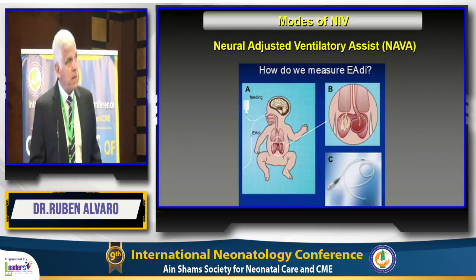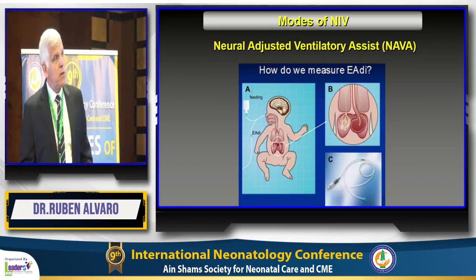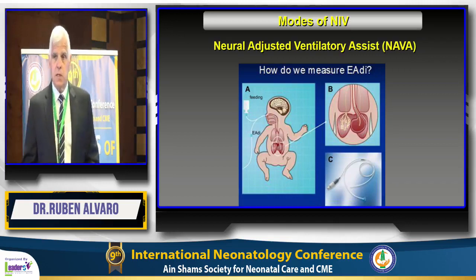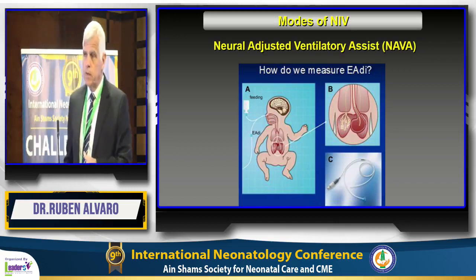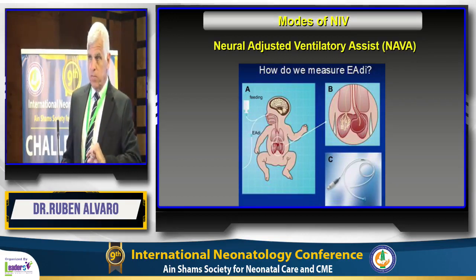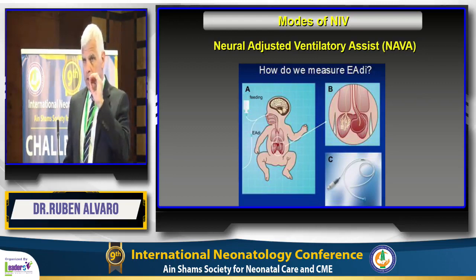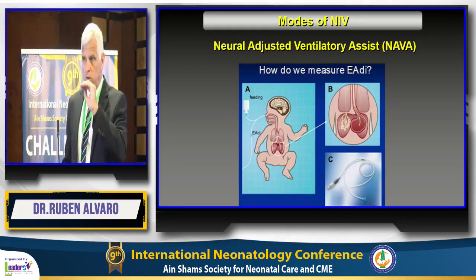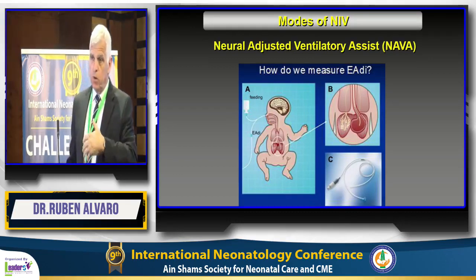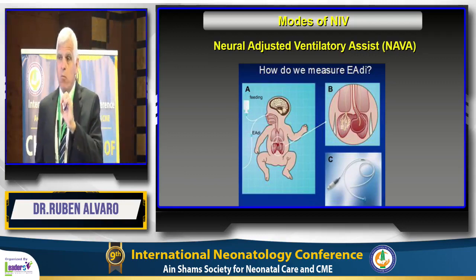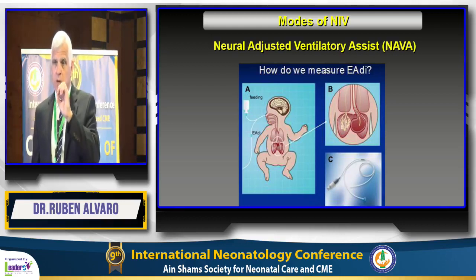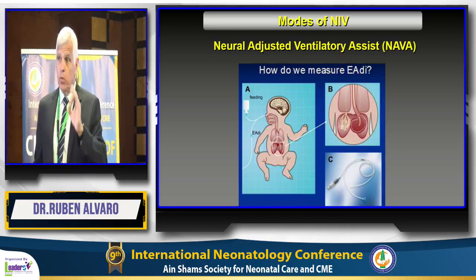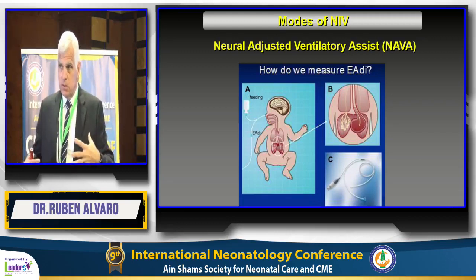You have an electrode that will detect the electrical activity of the diaphragm. It's basically a nasal tube with a sensor that sits behind the heart, just on top of the diaphragm. That sensor picks up activity of the diaphragm, so it synchronizes delivery of the positive pressure breath when the diaphragm is activated by the baby's spontaneous breathing, and also measures how much activity it gets from the diaphragm. So it assists with synchronization of the timing of the breath, but also how much assist the baby will need according to how much power the diaphragm generates.